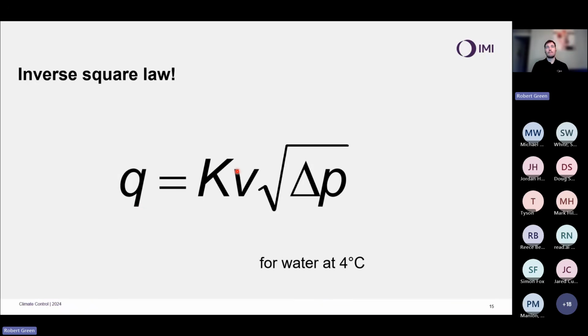Now, the Kv is the capacity for flow. Going back to our electronics, that is equal to the resistance. It is the inverse, actually. So a higher capacity for flow directly leads to a higher flow for a given differential pressure, or a lower differential pressure requirement for a given flow, multiplied by the square root of differential pressure.